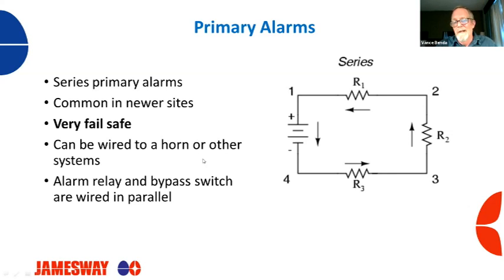This system too can be wired to a horn, but nowadays with all the high technology, a lot of times we're connecting them to tone generators, intercom systems, strobe lights. We can do a lot of things because we're using relays, and the relays will isolate whatever you want to do from what we're doing with our alarm system. And even though this is a series alarm, the alarm relay and bypass switch are wired in parallel. So if the bypass switch were here, it would be wired from this point to here. The electricity would go through the relay, or if you bypass the machine, it could go through the switch. But we'll get to that in just a minute.